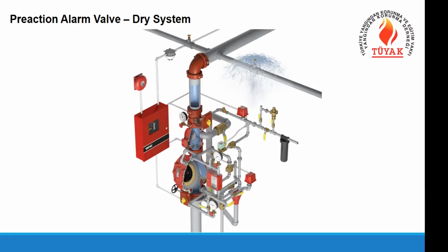When a sprinkler breaks accidentally, the system gives you an alarm that yes, here there is a problem, a sprinkler is open, but the detector doesn't give us a smoke alarm, so there is no fire. So in order to be a fire, two actions are needed. So this is called pre-action alarm valves. It gives you information that there is a problem at first, and if one of the systems, like detectors or sprinklers, has not operated, it will not release water inside the room. So this is a pre-action alarm valve system.